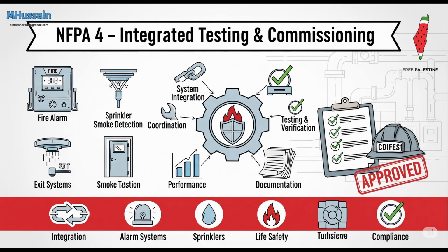Can you give us an example of limited integration where maybe a plan document isn't needed? Sure. Think of maybe a smaller building. It only has a basic sprinkler system, a fire alarm system that monitors the sprinklers, and maybe elevators that recall on an alarm. Pretty standard stuff. Right. The integration points there, like water flow activating the fire alarm, or a lobby smoke detector recalling the elevator, those connections are often already tested as part of the individual system testing required by other standards, like NFPA 72 for the fire alarm. Ah, so the integration points get covered during the routine fire alarm or sprinkler tests anyway. Often, yes. So in that case, NFPA 4 says you might not need a separate dedicated integrated test plan document on top of that, but the integration itself still absolutely gets verified.